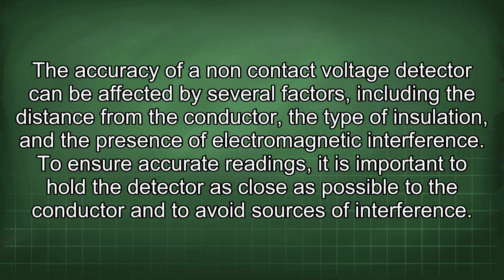The accuracy of a non-contact voltage detector can be affected by several factors, including the distance from the conductor, the type of insulation, and the presence of electromagnetic interference. To ensure accurate readings, it is important to hold the detector as close as possible to the conductor and to avoid sources of interference.